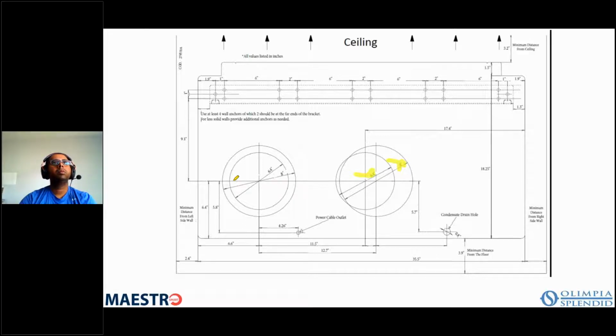Now you do lose a little bit of efficiency and a little bit of capacity, but it's very, very minor. I mean, it's measurable, but it's not significant. So the thing to keep in mind is, if at all possible, you want to use those 8-inch holes and not the 6-inch holes. And then you'll also see over here on the Smart, here's where your drain will be. On the Pro, it's kind of more over here, okay? But the templates for each of them will properly mark that for you, okay?